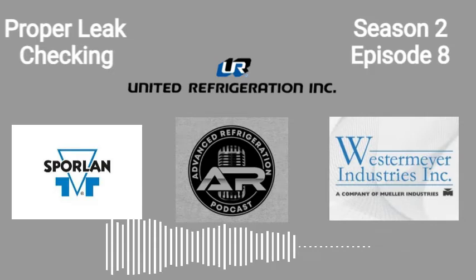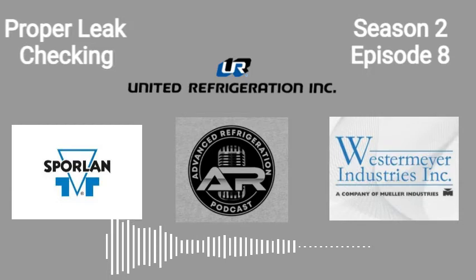So do you do the cases first? Generally, I start at the rack first. I'll warm it up and walk in. Obviously, if I walk in and it goes nuts, I'm going to respond to that. But I generally go straight up to the rack and leak check it, because the majority of the leaks are in the rack room. That's where the most vibration is, the most piping, all the valves, flare nuts, stuff like that. I spend my time going thoroughly through the rack.